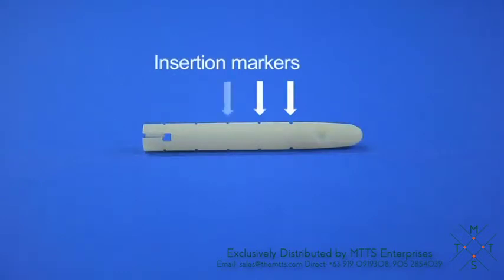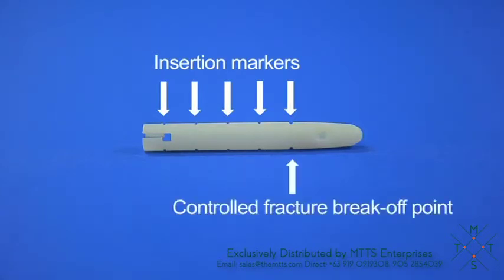There are five one-centimeter insertion markers for easy identification of insertion depth from the center of the capsule hole. The first marker is also a controlled fracture break-off point to enable easy access for retrieval of the specimen.